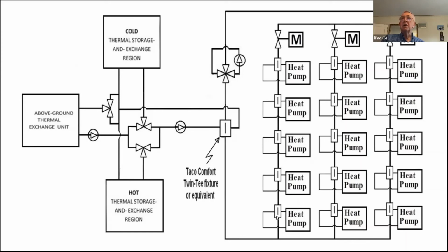So what can be done is periodically this flow direction can be reversed. So let's say it reverses once per day or once per week. When the flow is clockwise, the top heat pumps have the best result. When the flow is counterclockwise, the bottom heat pumps have the best result. So everybody gets equalized in terms of efficiency and capacity over a long enough time period. This kind of reversal has been done for different kinds of thermal distribution products, but as far as I know, it hasn't been done yet for an array of heat pumps, such as shown here. And there's a lot more engineering work that needs to be done to optimize everything regarding that.